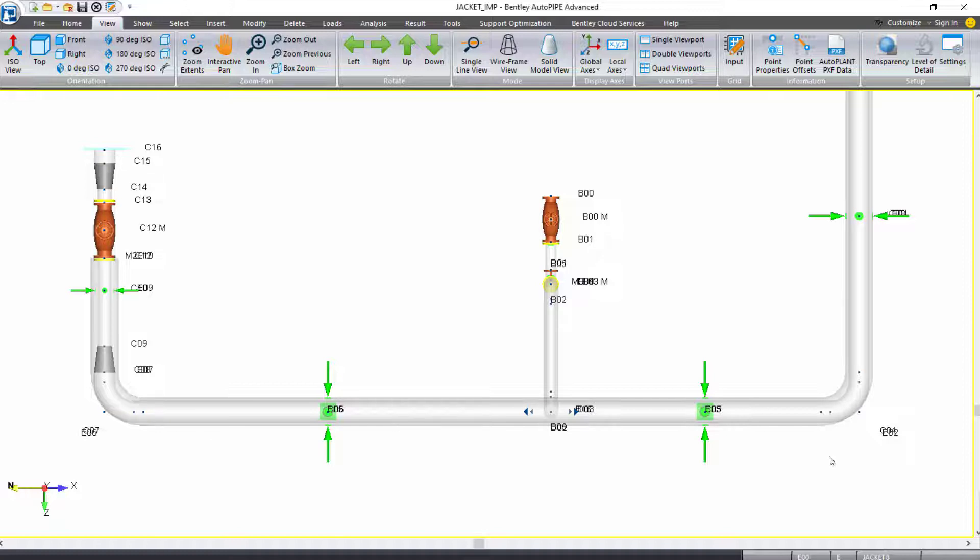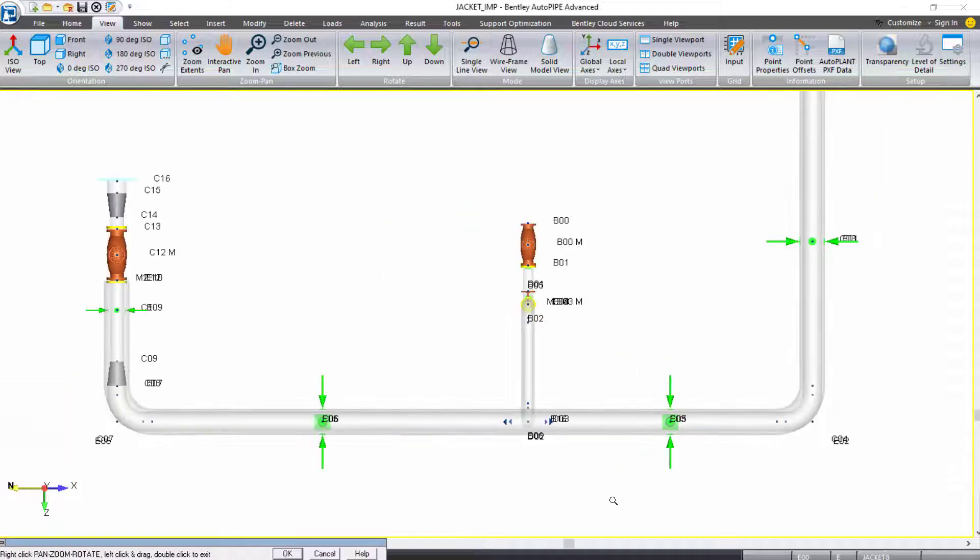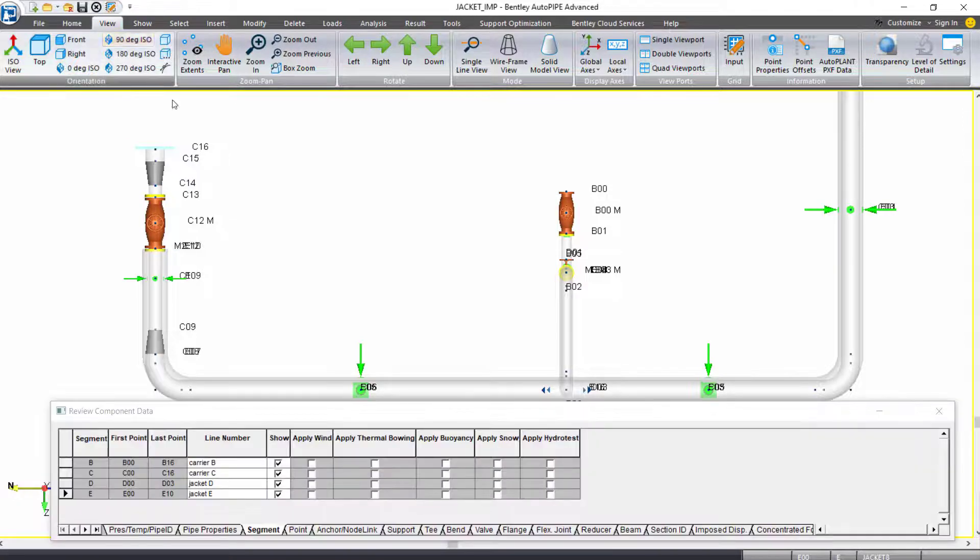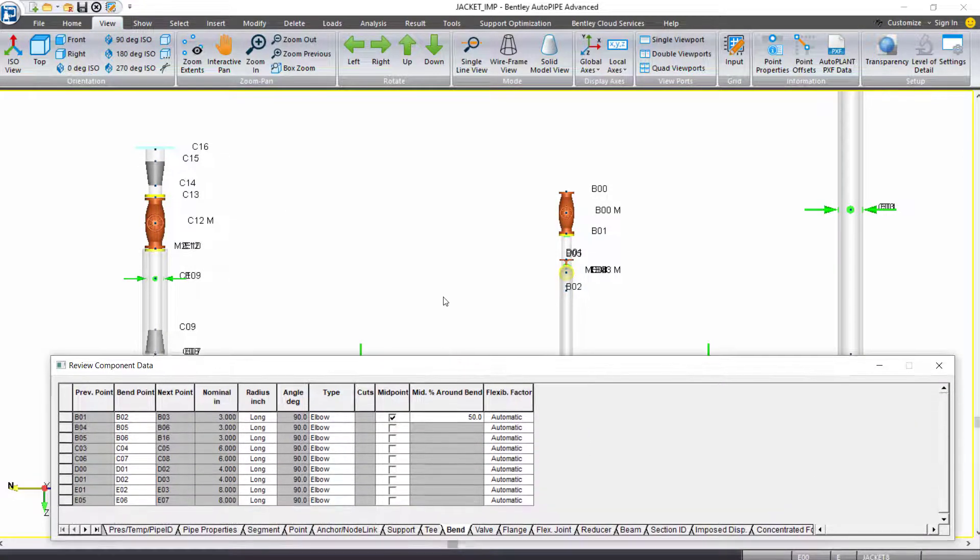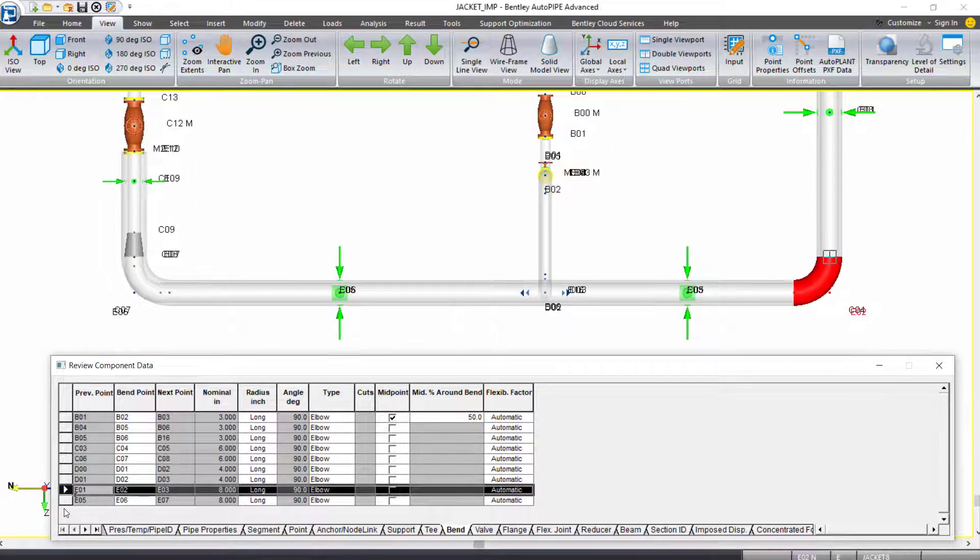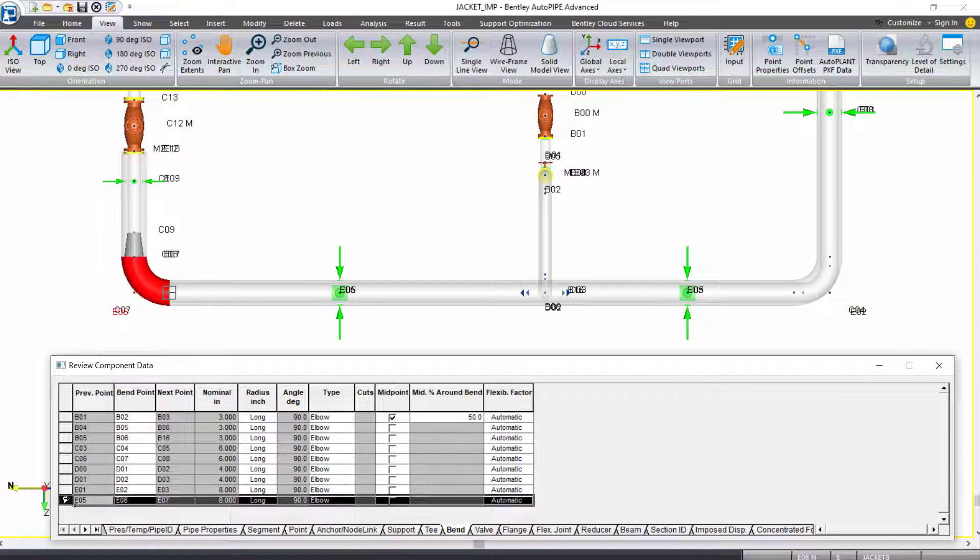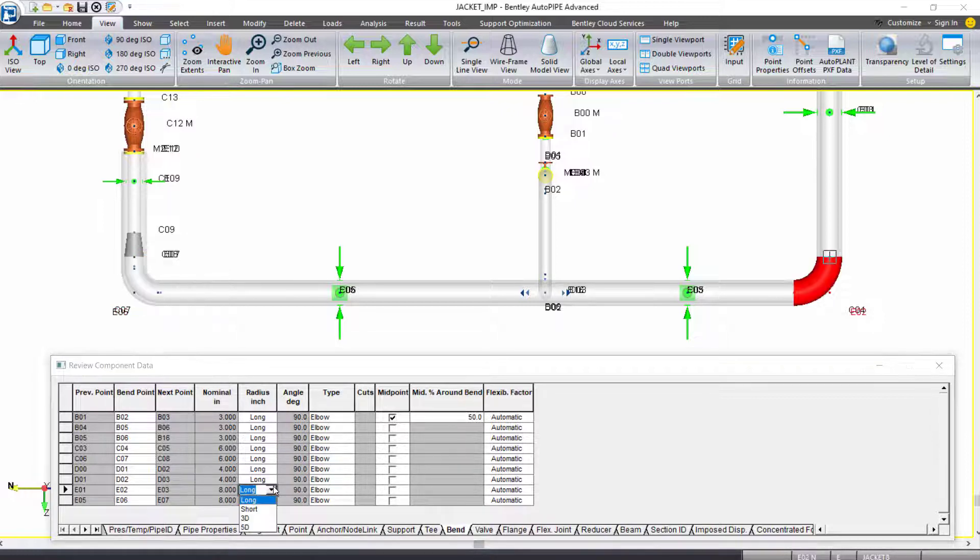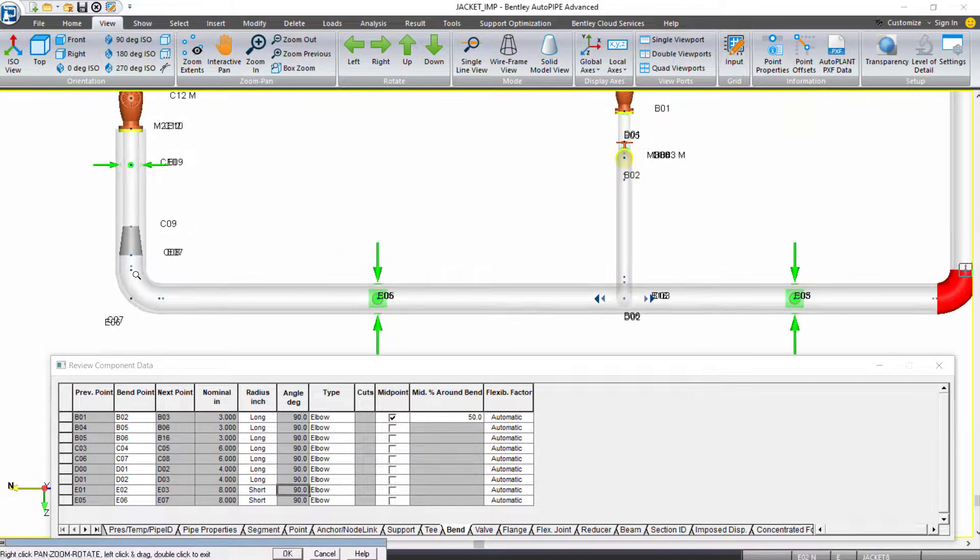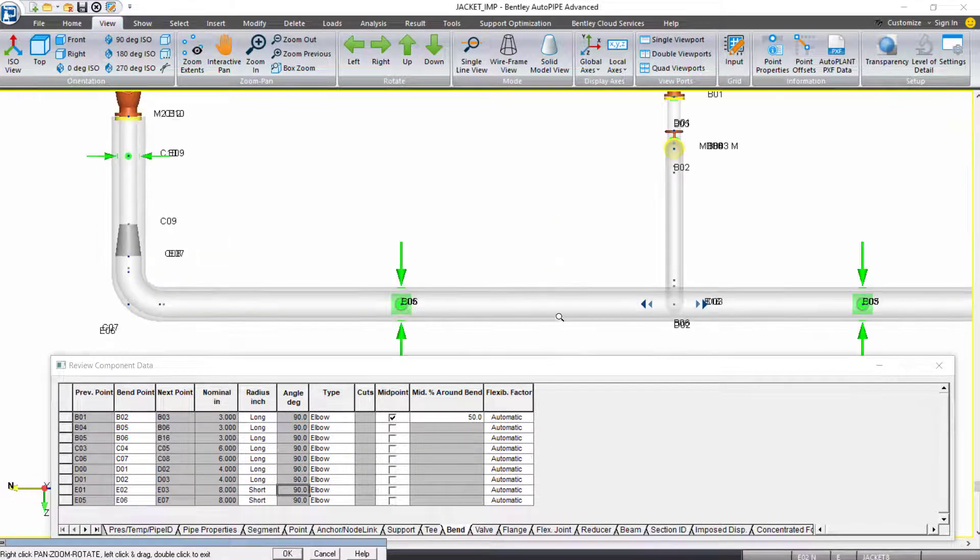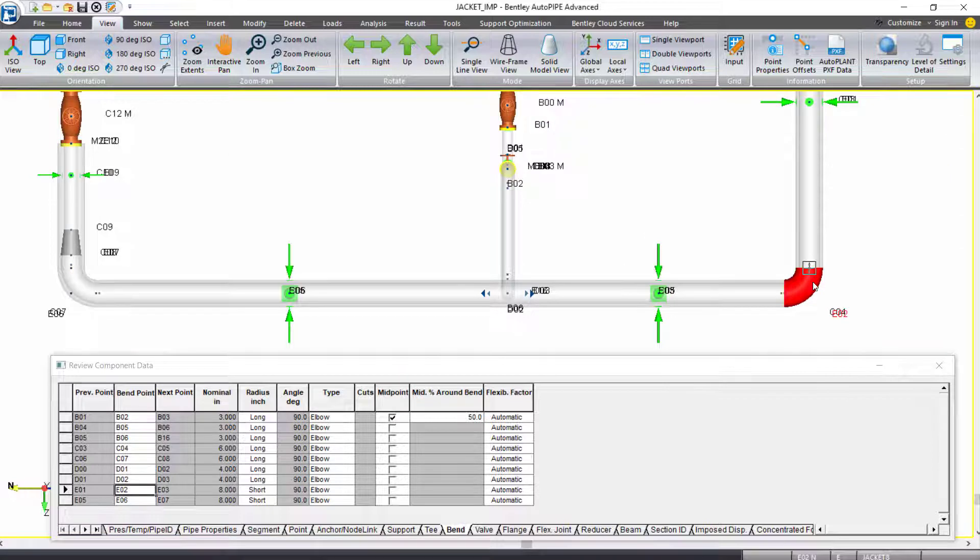so that these bends line up a little bit better to start. I'll open my input grid, and this time I'm going to select my bend tab. I want to navigate to my bends on my E piping, my segment E piping, which represents my jacket. And I'm going to change the radius to a short radius bend for both of these. When I change that radius, you can just see that everything fits a little bit better to start.